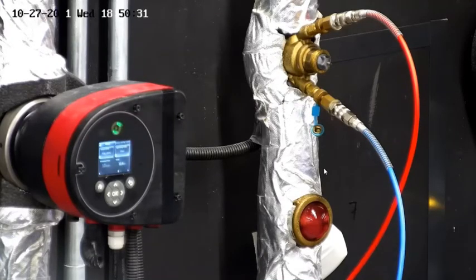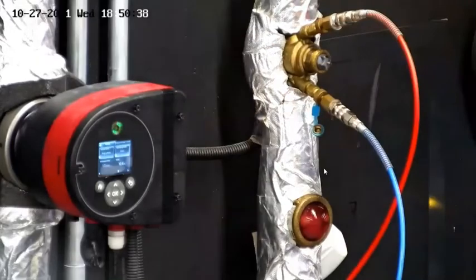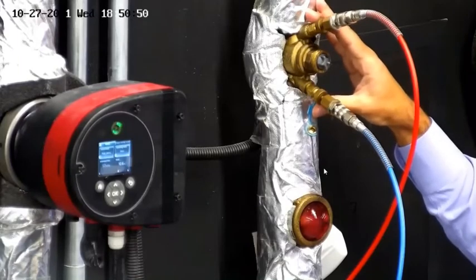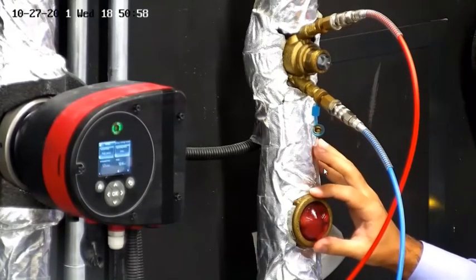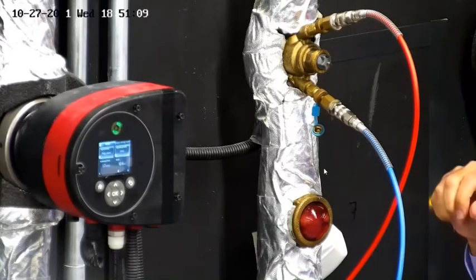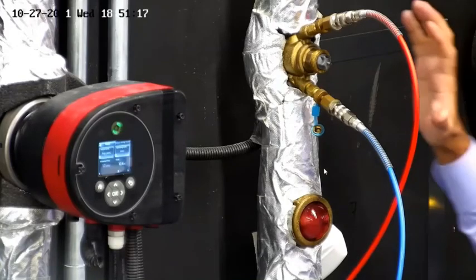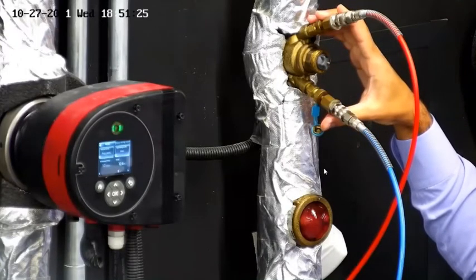So basically what you see now on this view is a pump which is driving the flow of the water from the supply line, a return section which is equipped with a PICV, the N25 high flow version, a sight flow glass which is a visual proof of the flow, and there are many more items within the circuit which are available for temperature measurement, pressure measurement, as well as different provisions for flow rate verification, such like the FMD. Our concern here is to have a look at the differential pressure across the PICV and the measured flow rate according to the data sheets.